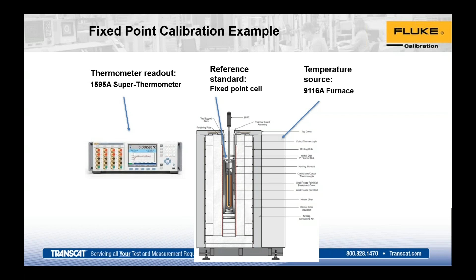So again, going back to the discussion, you've got to have the standards, or I should say the fixed point cells become your reference standards. But then you've got to have your temperature source to maintain this cell, and also a good way to get the data out of the cell. So it takes a few different pieces. There are also pieces that people don't realize on the maintenance side for maintaining the fixed points. That's a good discussion if you're looking to get into this. With some of these furnace heat sources, you do have to have separate probes that you use to profile the furnace and set the cell up, to make sure that you don't inadvertently break it or cause a gradient that can give you problems down the road.